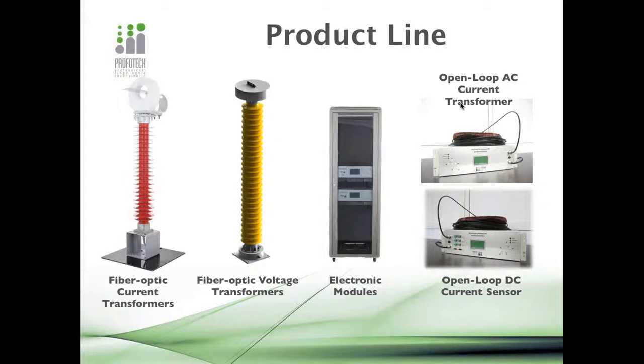The second is the fiber optic voltage transformer, the high voltage fiber optic voltage transformer. The electronic modules are used to interconnect the sensor, the transformer installed at the switchyard, and all the secondary devices. And these electronic modules have this IEC 61850-9-2 interface. And also you can see to the right is the open loop AC current transformer. This one can be used for sensing the AC current and interfacing with the protective relays or with revenue meters.